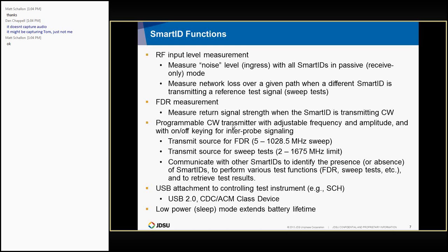Okay. The next item is the programmable transmitter, where I'm kind of repeating the ranges of it. The FDR, we actually run a 1024-point sweep from 5 to 1028.5 megahertz. The transmitter also acts as a source for sweep tests, which we do a number of different sweep tests depending on the application being tested. And that is also used to communicate with other Smart IDs. Okay, and one last thing I'm mentioning here is there's a USB attachment for the master probe. It's a USB 2.0 connection with a CDC ACM class device, and the firmware also features a low power sleep mode that extends the battery life on it.